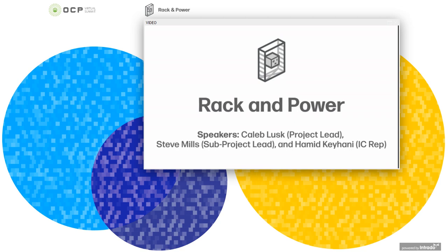I can talk about that real quick. There are two different groups working on new interconnects for rack and power. Both of them are for the power shelf. There is a universal input connector into the power shelf, and then there is a 48-volt output connector that takes the power from the power shelf and puts it onto the bus bar for all the other components in the IT and the rack to use.